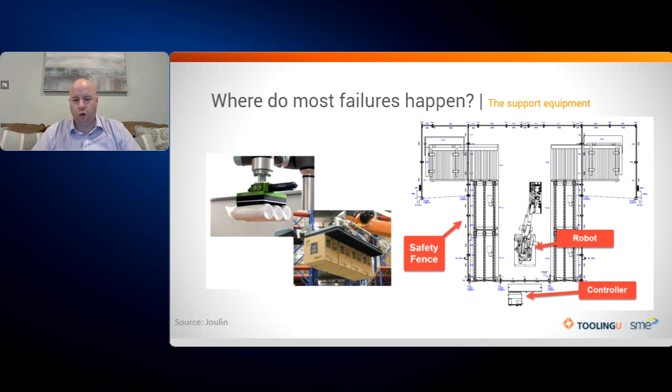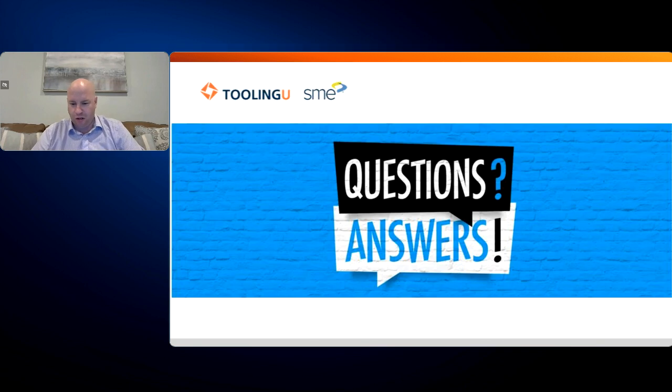And then, of course, the controller and the support cabinet may need compressed air to blow the dust out. I highly recommend that when you are using control cabinets that there are air conditioners put on there because those frequency drives do produce a lot of heat. So those are just some minor things that can be done to avoid a major breakdown or downtime. All right, so that's all I have on this slide. And the next one is to go into questions.